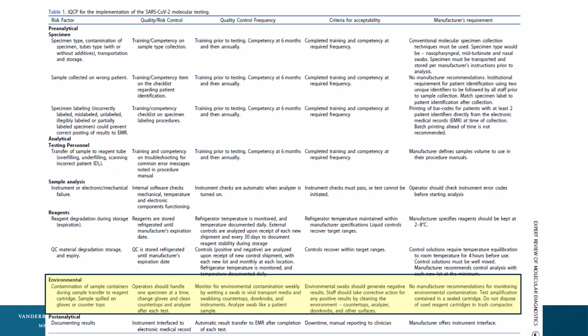This was our risk management table, and you can see in yellow the risk of contamination, and we implemented those environmental controls, despite the fact that the manufacturer didn't have recommendations like this. That was something additional that, as an institution, we implemented. So we conducted a risk assessment. Our quality control plan was additional quality controls, this environmental control. After we implemented that, we assessed how well this is really working.